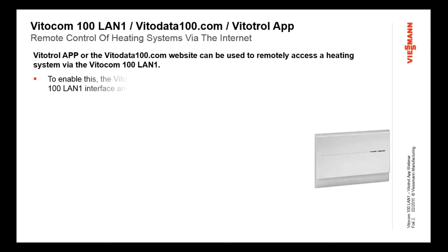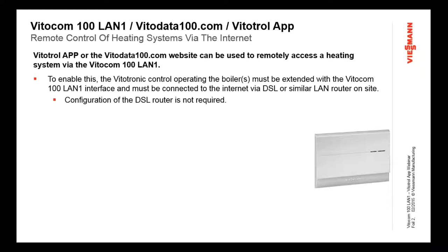So we're going to look at both situations. To enable this, we have to have some device to connect the boiler to the internet. That is the Vitocom 100 LAN1 interface. It is connected to the boiler through a LAN connection, and then it's connected to the internet connection in the home or the building through a DSL or similar internet connectivity. And once that's done, then the system will find the Vitocom unit on the internet. There usually aren't any modifications that have to be made to the DSL router. We're going to be hooking up to it just the way it is, so there's nothing you have to know about internet connectivity other than to hook up a cable like you would plug in your computer.